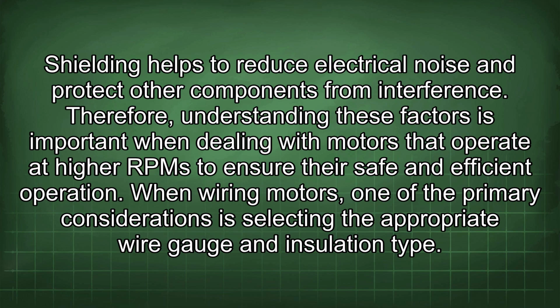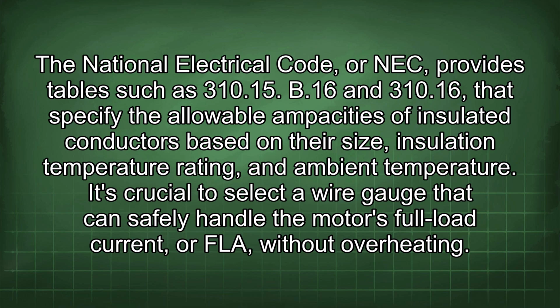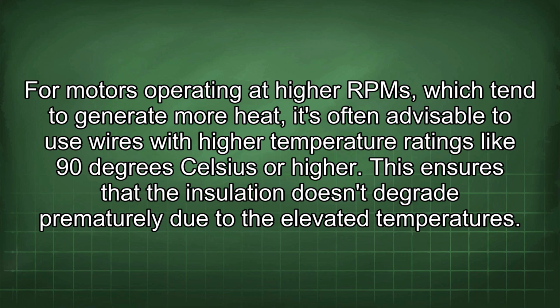When wiring motors, one of the primary considerations is selecting the appropriate wire gauge and insulation type. The National Electrical Code, or NEC, provides tables such as 310.15(B)(16) and 310.16 that specify the allowable ampacities of insulated conductors based on their size, insulation temperature rating, and ambient temperature. It's crucial to select a wire gauge that can safely handle the motor's full load current, or FLA, without overheating. For motors operating at higher RPM, which tend to generate more heat, it's often advisable to use wires with higher temperature ratings like 90 degrees Celsius or higher. This ensures that the insulation doesn't degrade prematurely due to the elevated temperatures.